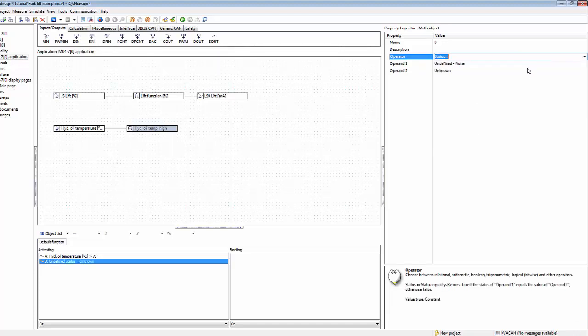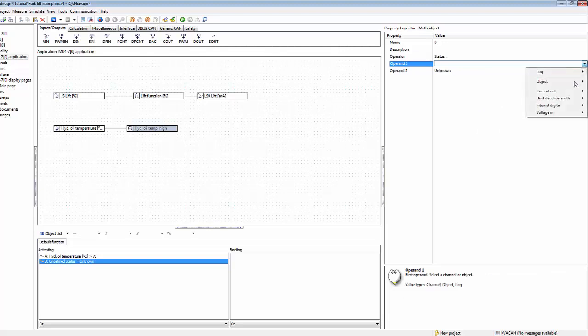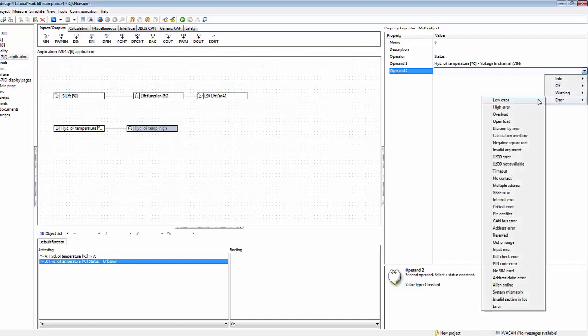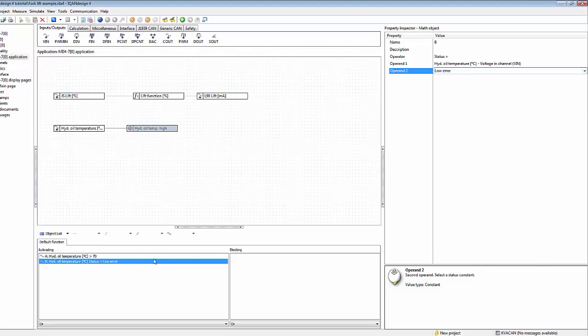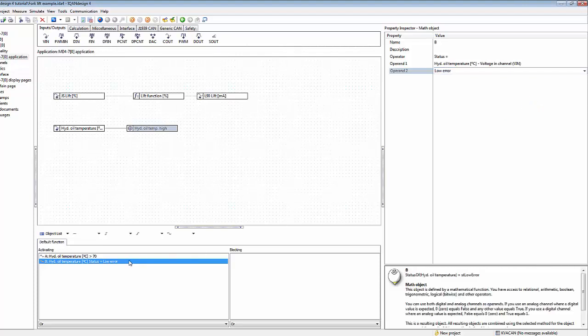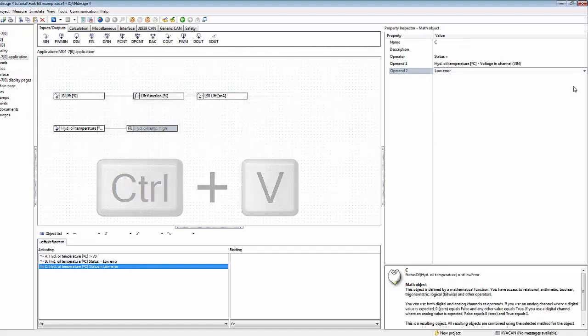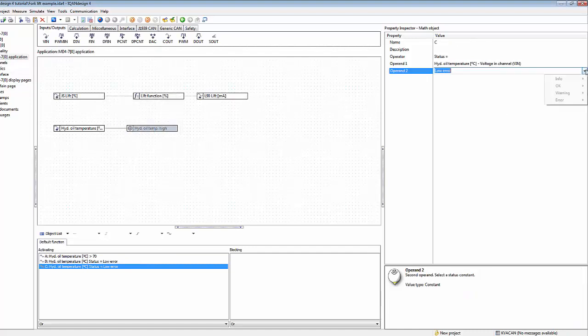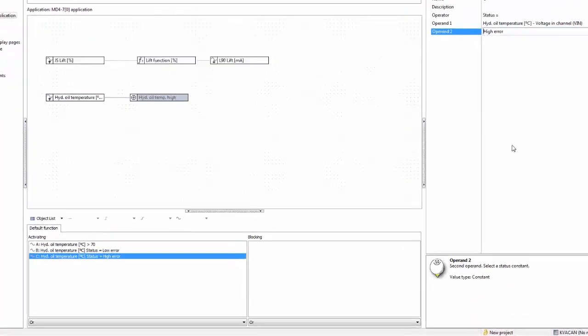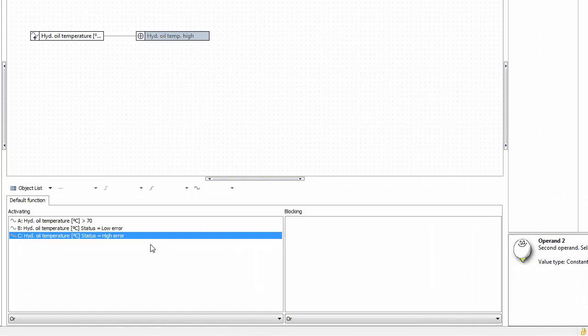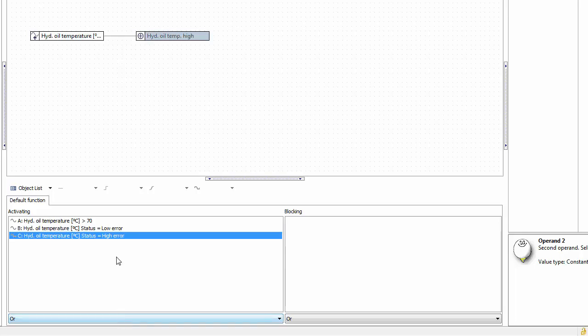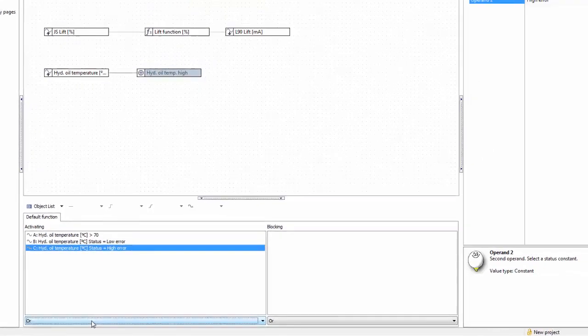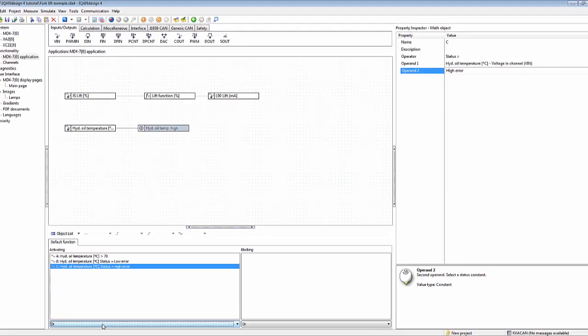We select our voltage input channel and we select which status type. I know this is an error, so I select it from the list of errors here. If we just copy-paste this, we also select the high error as that's one of the errors that will give this warning. These three conditions are now combined with this object group method, the OR method, and that's exactly what we want. So we can try that once again in the simulator.